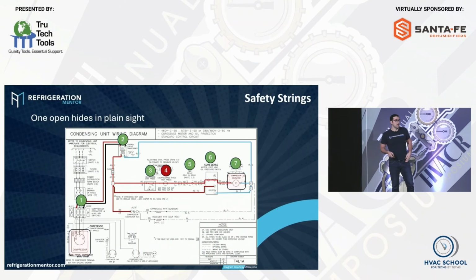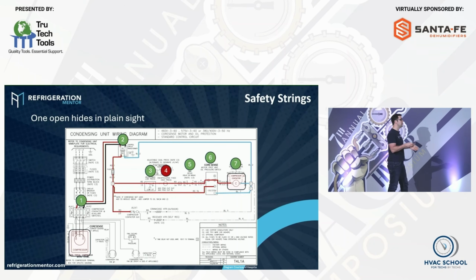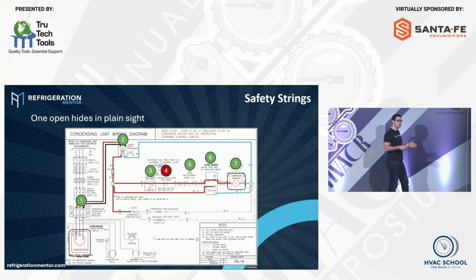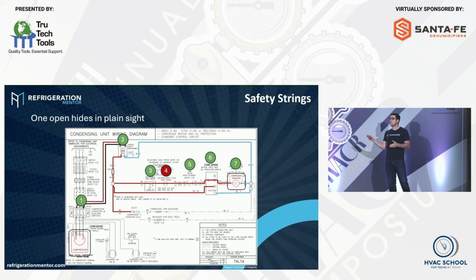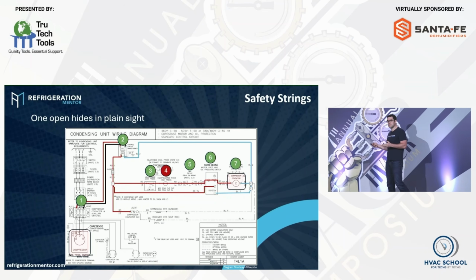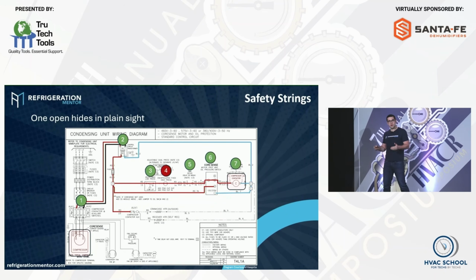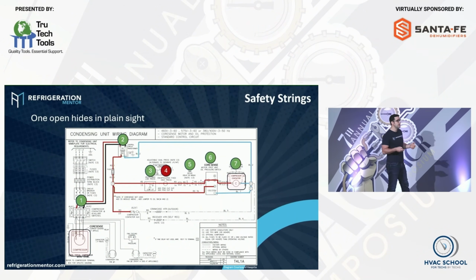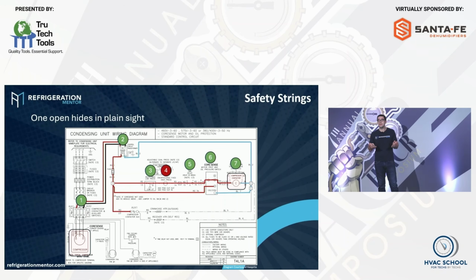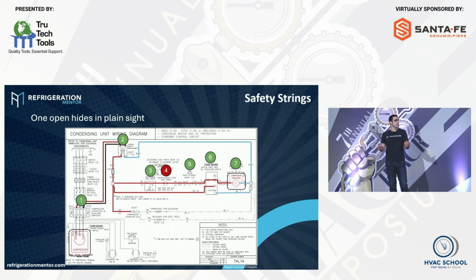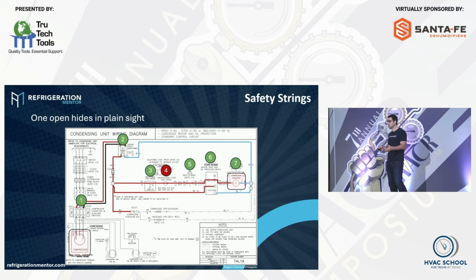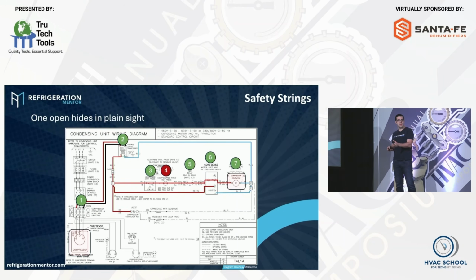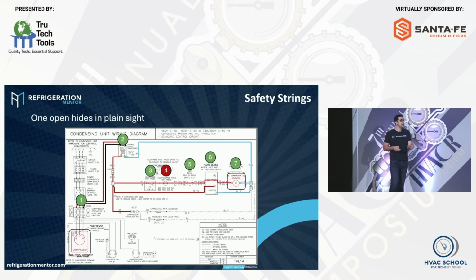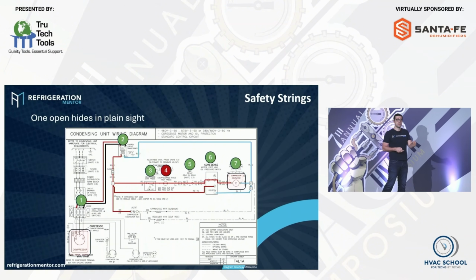Our safety string, one open hides in plain sight. In a supermarket application, or even an application like this, if you have something that trips off, we usually get a call about something like a compressor proof failure or safety line alarm. When we get out there, how do we troubleshoot this? It hides in plain sight because now we have multiple circuits. We have a low pressure control, maybe a high pressure control. We have an oil safety control. We have an over temperature control, maybe a discharge line temperature control, maybe a low ambient control in it.